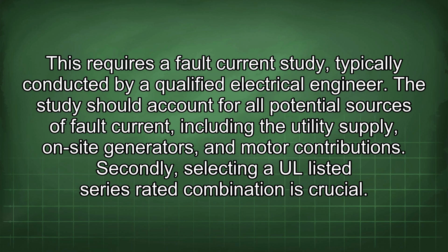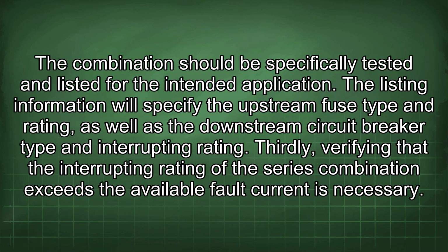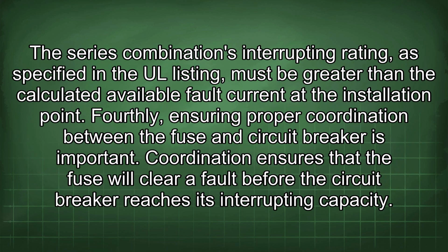Secondly, selecting a UL-listed series-rated combination is crucial. The combination should be specifically tested and listed for the intended application. The listing information will specify the upstream fuse type and rating, as well as the downstream circuit breaker type and interrupting rating. Thirdly, verifying that the interrupting rating of the series combination exceeds the available fault current is necessary. The series combination's interrupting rating, as specified in the UL listing, must be greater than the calculated available fault current at the installation point.